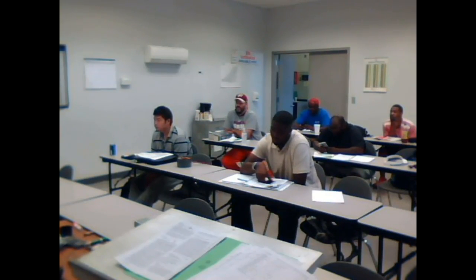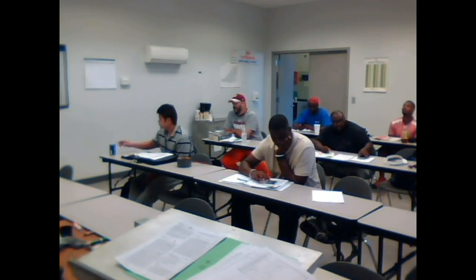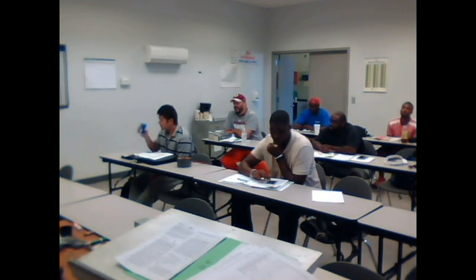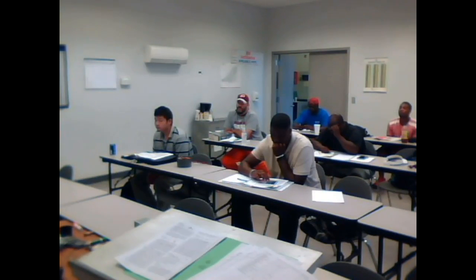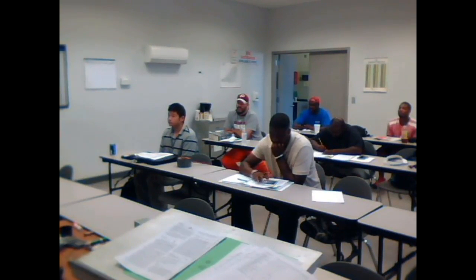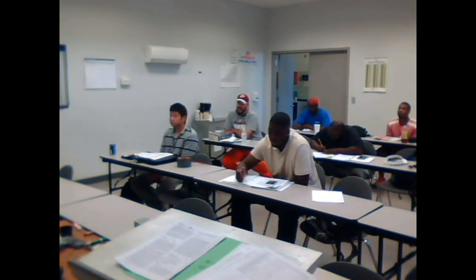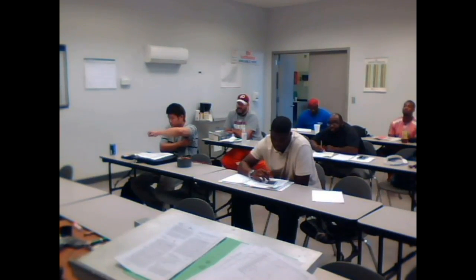All right, so everybody understand how to read this VA. And they're saying we're exceeding our numbers. And once we exceed our number, we won't maintain our voltage. Okay? So it's pretty simple. I mean, if you see a problem with a 40, shoot, I'm going to give me an 80. Now, you go, well, why didn't they do it? Because they're selling under rules from the government, and they want their piece of equipment to consume as little electricity as possible. In other words, it's efficient. I put a bigger transformer in there, it's going to consume more electricity. I mean, not a ton, but you got to get every penny, every ounce you can on those things to make them seem efficient. Okay?